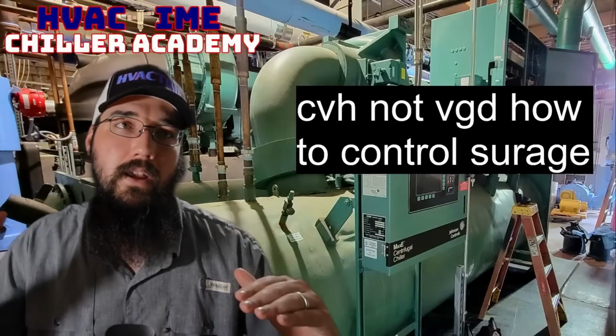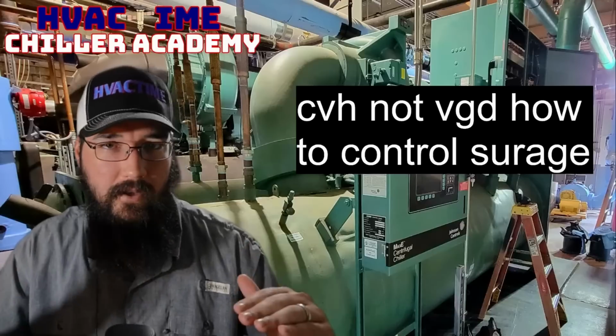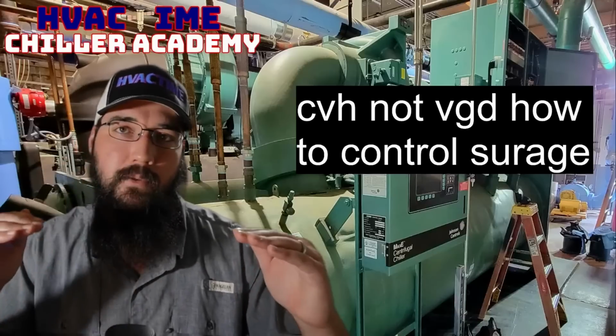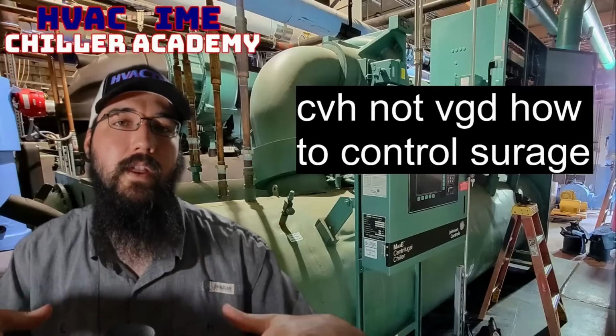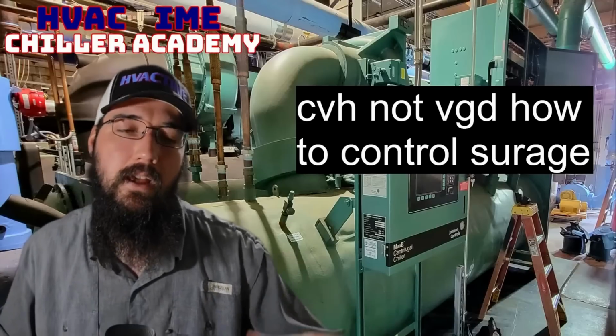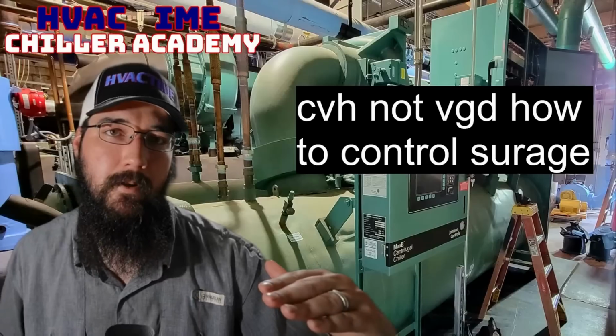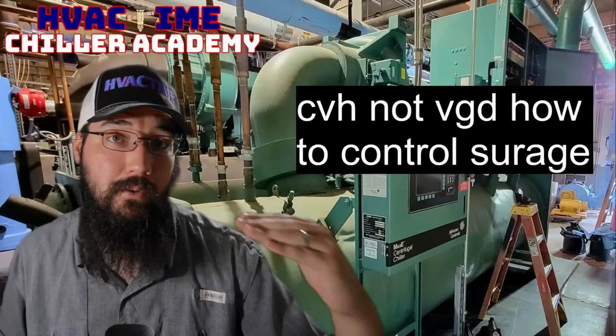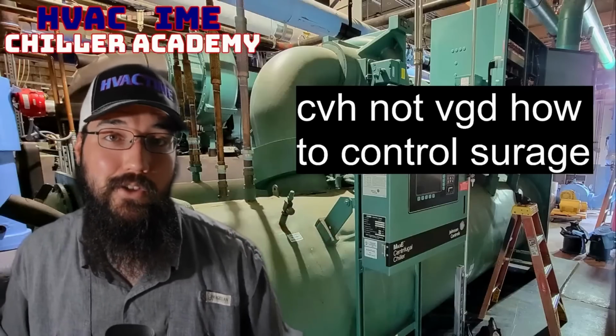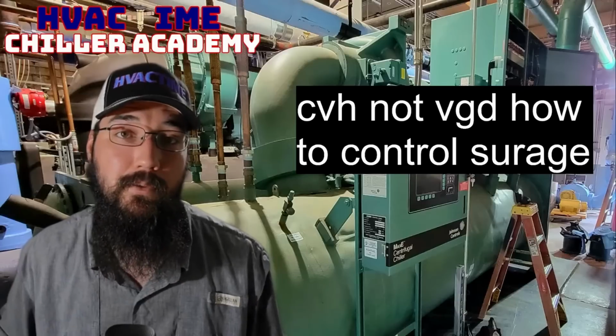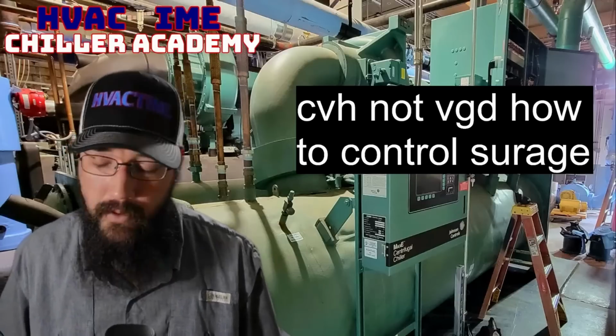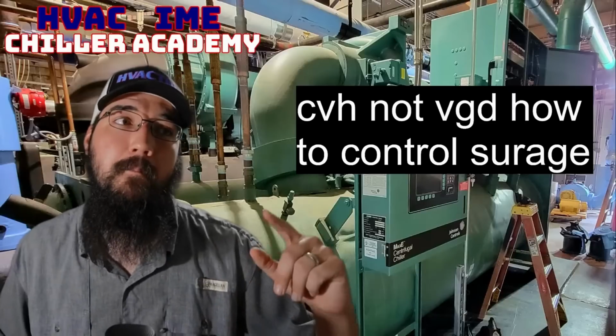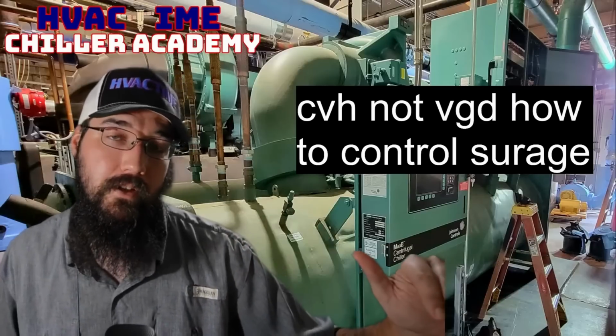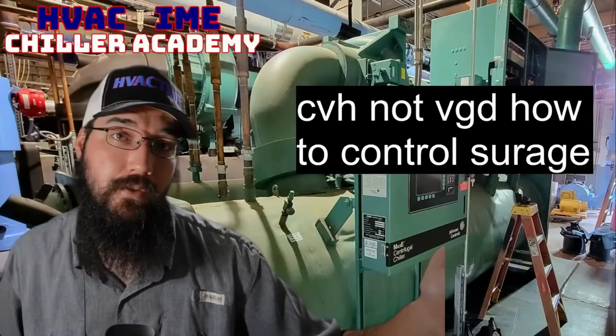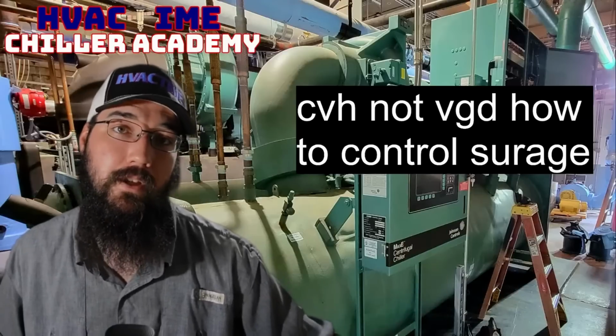I will find where that safe spot is, where I can comfortably leave this machine online to run without pushing into a surge immediately. And I will just set that current limit there. There's been situations where that was 50%. The most that chiller could ramp up to is 50%. Could it make leaving water set point? No, it couldn't. But 50 degrees leaving was better than nothing at all in this circumstance, right?